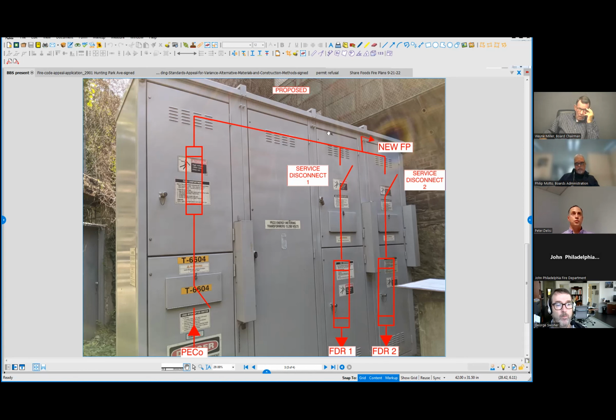All we have to do is have this switch be opened up, or these fuses blow out, where the fire pump will be useless in this fashion if it gets approved. Well, how many different failure scenarios do we need to account for? I mean, we're already postulating that there's a fire within the building. We tap this gear ahead of the outside main service disconnect, and then that eliminates a second failure. You're saying that this gear is also failing. The tap ahead of the service disconnect, and then we take it up and over and avoid all of them. There's one fail, possible two fails, and three fails if we do it right.